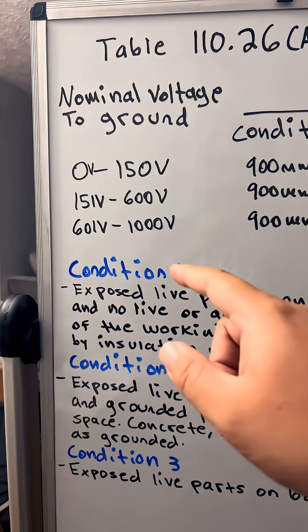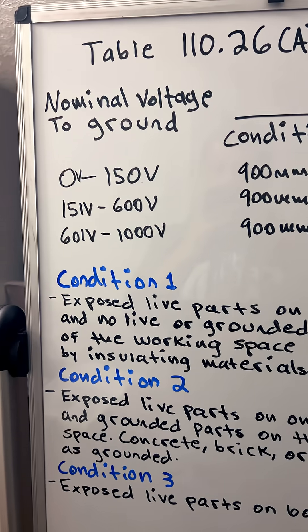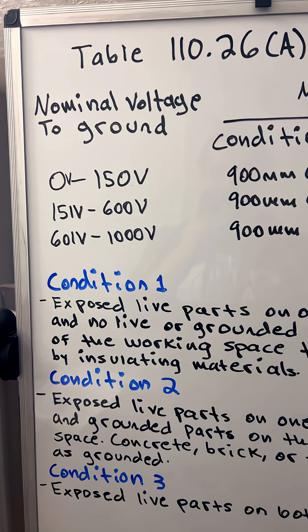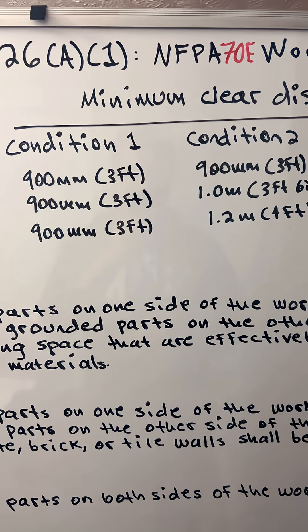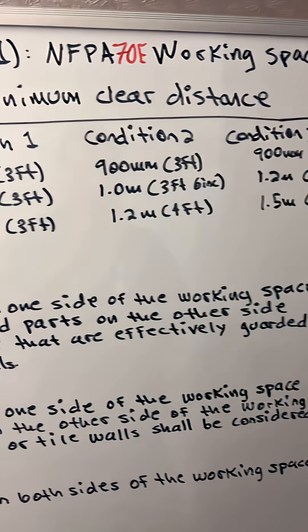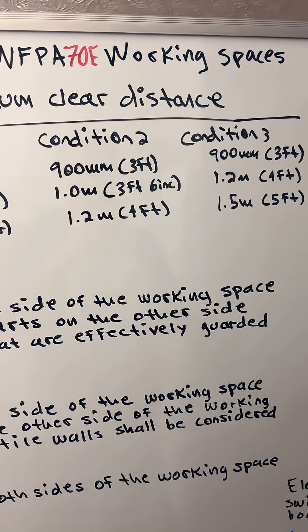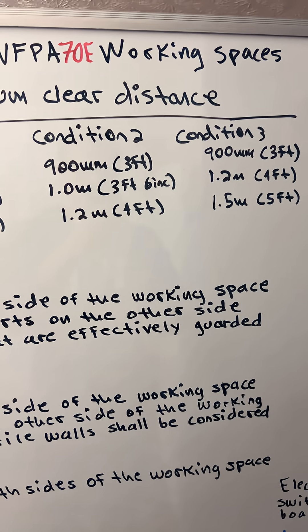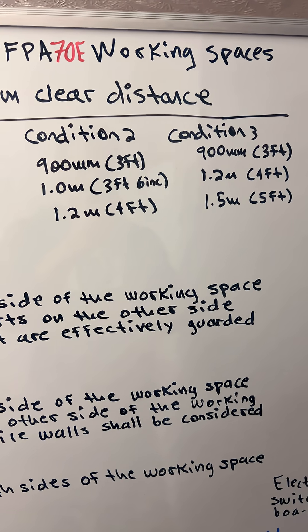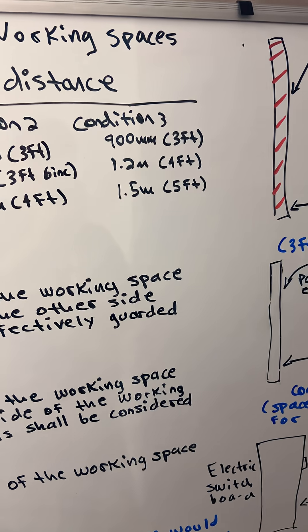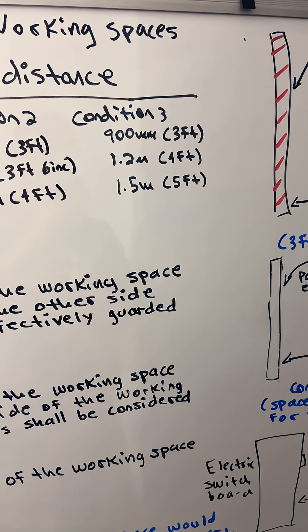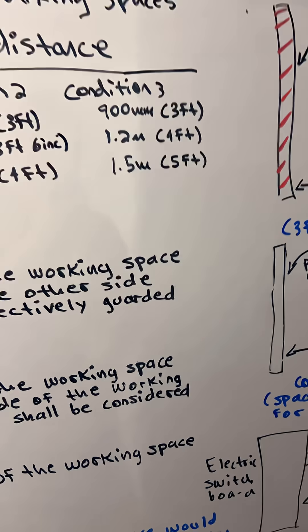And for 601 volts to 1,000 volts: condition 1 is 3 feet, condition 2 is 1.2 meters or 4 feet, and condition 3 is 1.5 meters or 5 feet.